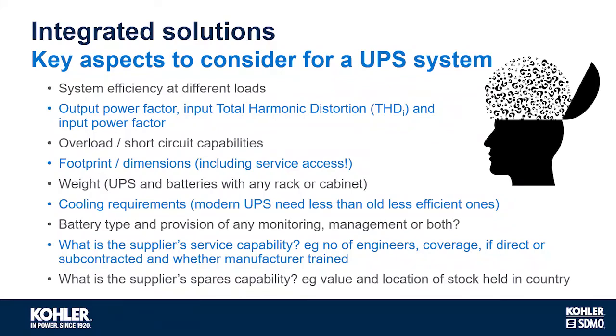Now, UPSs have evolved, and they're getting lighter and smaller. However, the batteries typically now are still VRLA, and they'll be housed in a rack or cabinet and can be extremely heavy. So that is very important to understand from the beginning. Like I said, modern UPSs are becoming much more efficient, but they still need cooling. They typically don't need as much cooling as the batteries.